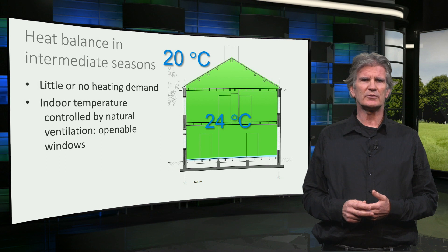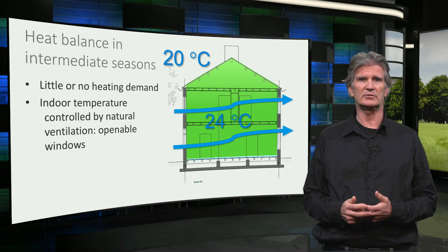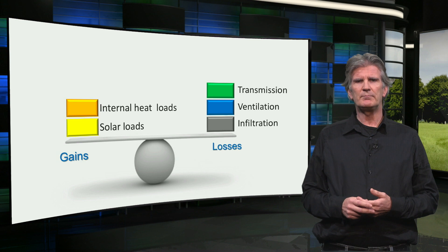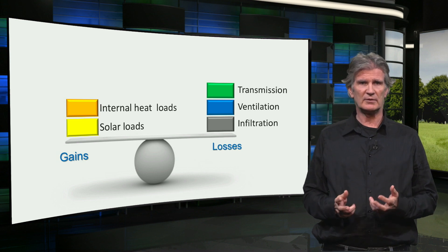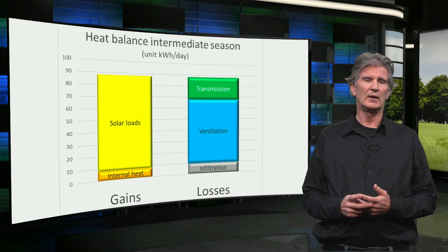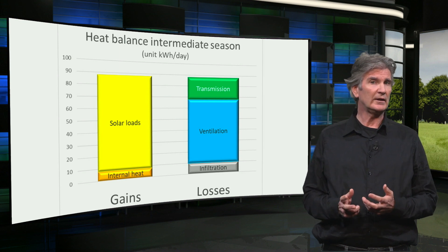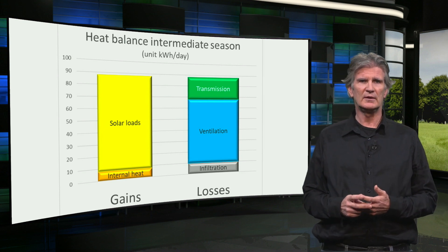In this case the indoor temperature is slightly higher than the outdoor temperature, and the indoor temperature is controlled by natural ventilation — just opening the windows. This is what the heat balance looks like in an intermediate season. On the gain side there are the solar loads and internal loads, and on the loss side there are transmission, ventilation, and infiltration losses. If we look at a typical day in spring or autumn, there is no heating or cooling — the heat gains by the sun and internal loads are balanced by the transmission loss and mainly the ventilation loss through the windows.